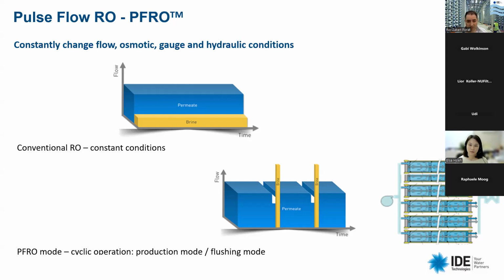Of course, I cannot mention the company, but I can mention a FAB where we fitted it in parallel to an existing standard reverse osmosis unit that was only able to work at 30% recovery with a lot of CIPs, a monthly CIP. This system worked continuously and is still working continuously for 3 years now, with CIP only once a year and much higher recovery, double that of the standard one.